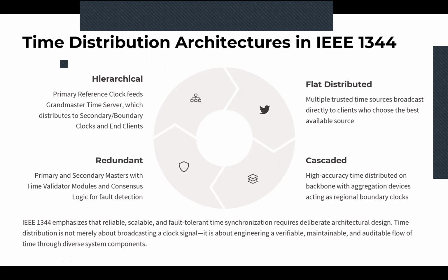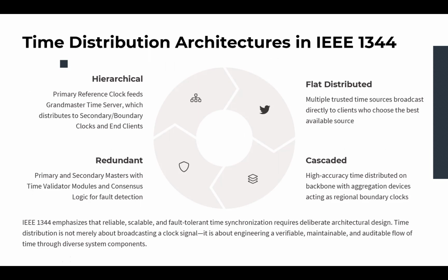Now, the time distribution architectures in IEEE 1344 include a variety of architectures. But why does the architecture matter? Because time, like a voltage or any kind of signal bandwidth, degrades over distance, noise, or any interference. So the design of your time distribution topology affects your system performance, system reliability, the scalability of the time synchronization, and the fault tolerance. It's not a one-size-fits-all architecture. Instead, IEEE 1344 enables a library of validated strategies. Let's talk about a few of them.